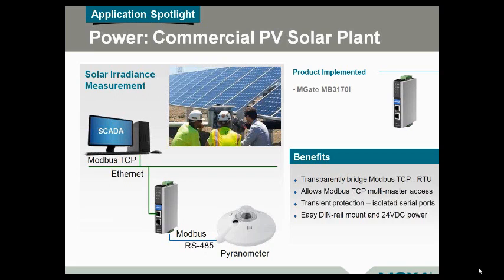We recently had, a few weeks back, a couple of fires within the mountains nearby here in Los Angeles, and with the soot that happens from that, that can settle on the solar panels and reduce the efficiency. And the only way you know about that is by being able to know how much power is being sent to you through the sun and how much is being produced. So you might use something like a pyranometer here to measure solar radiance, and by knowing here's how much we should be receiving and here's how much we're producing, you can find out that there's a problem within your system. That could be dirty solar panels, it could be a number of things.